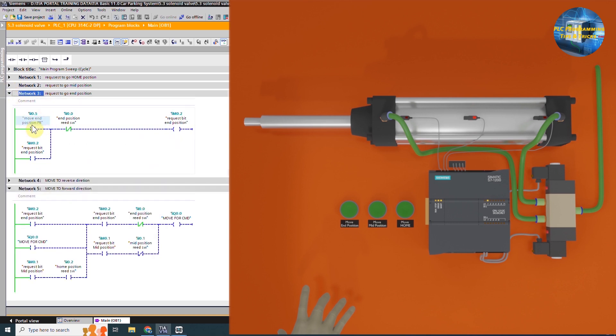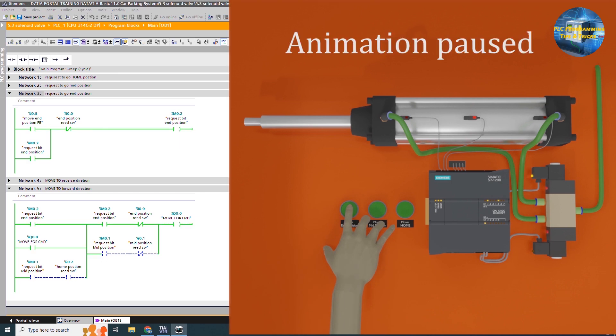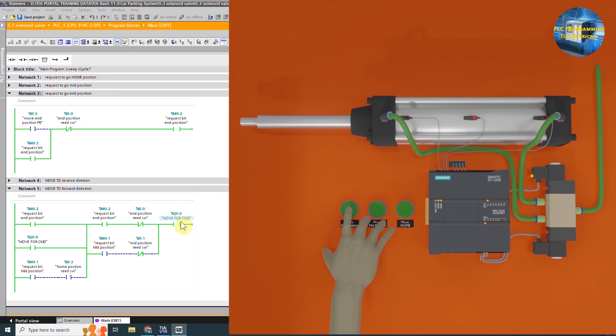Next, if we press the i0.5 end position push button, it will latch on the m0.2 end position request bit. In network 5, m0.2 latches on the forward command Q0.0 and the cylinder starts to move forward. As soon as the cylinder reaches the end position sensor i0.0, this normally closed contact opens and unlatches the PLC output Q0.0.